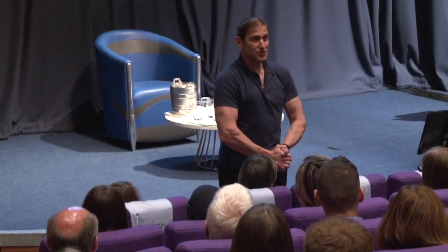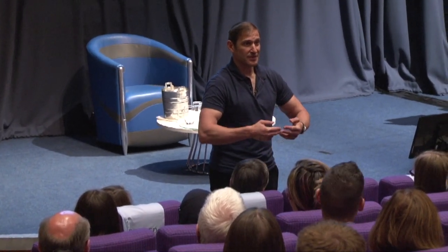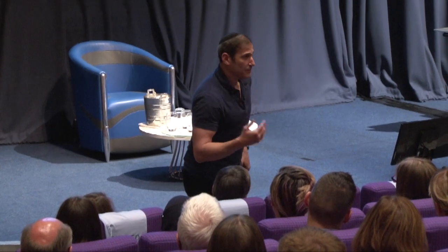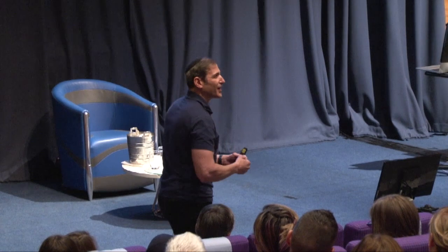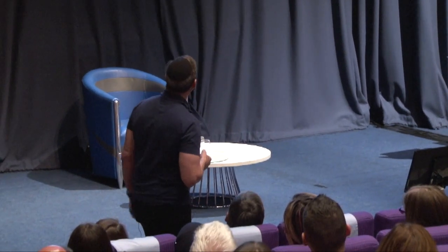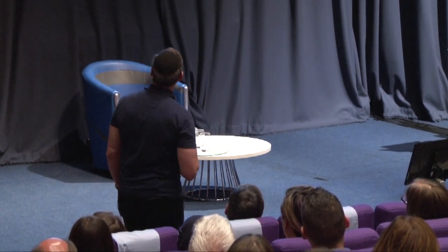But you know what you do get injuries from? This. And you can see it, right? Right there. It's where the surface area for that path is a very small, narrow area where the resistance might increase, and that's where you might have concerns about burns.